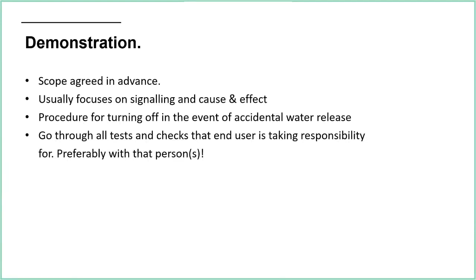Here's an important one here: procedure for turning off in the event of accidental water release. So we need to make this absolutely clear. This is in the event of accidental water release. If you've got a fire, then the building owner, the maintenance team, whoever, should not be messing with the sprinkler system. It's a fire, leave it to do its job, call the fire and rescue service out, and they'll deal with it. And when it's confirmed safe, then you can work together to turn it off. But this is in the event of accidental water release, when you're absolutely sure there's no fire. What do you do?